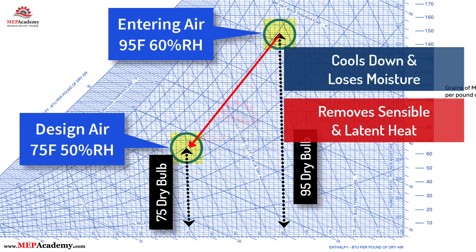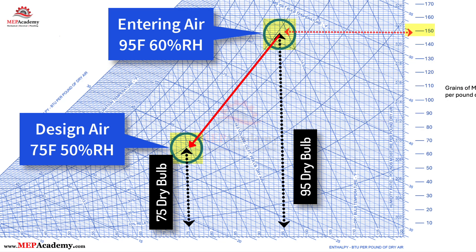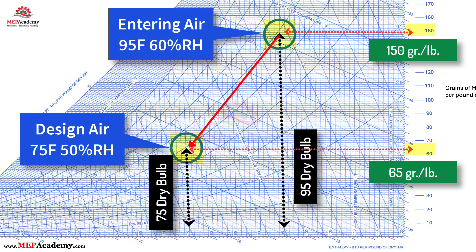At 95 degrees Fahrenheit and 60% relative humidity, the humidity ratio is about 150 grains per pound. At 75 degrees Fahrenheit and 50% relative humidity, it's about 65 grains per pound. So the cooling coil removes 85 grains of moisture per pound of dry air. This is a simple explanation of how the psychrometric chart is used to solve problems and determine what happens to the air at various conditions.